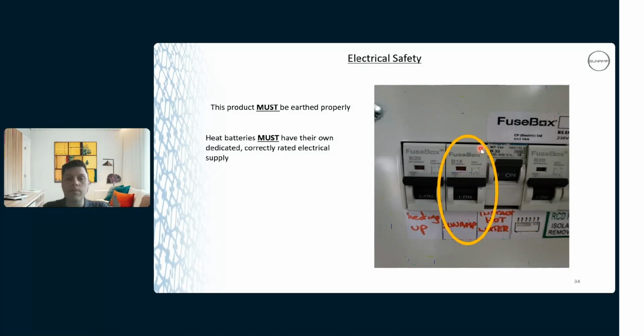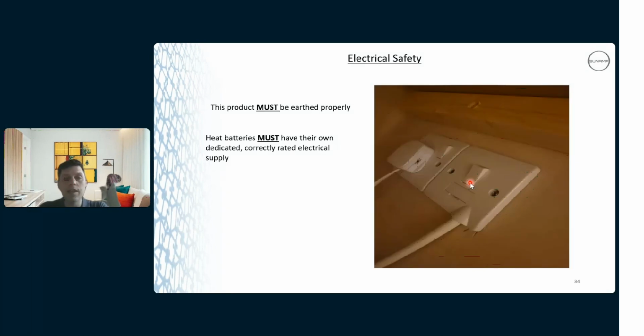There's a couple of sites that I've been to where the heat batteries are tying into the ring main circuit of the sockets and things like that. You're just going to give yourself problems. So we need a 60 amp breaker back at the fuse board. I've seen both of these scenarios: heat batteries wired into a plug socket, and heat batteries wired into a fused spur.